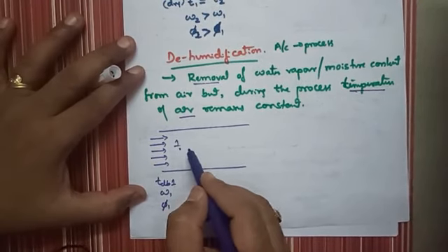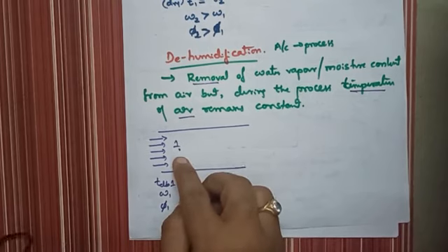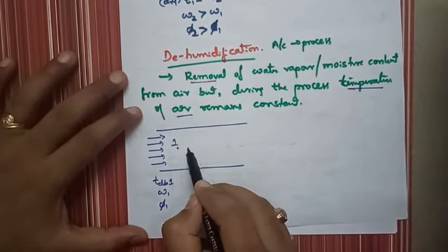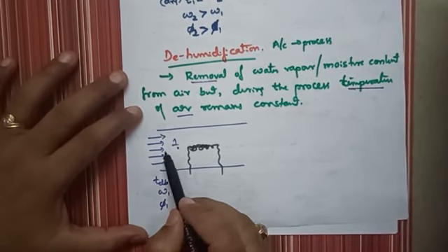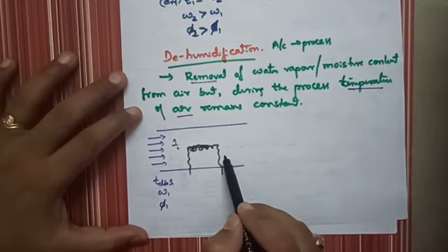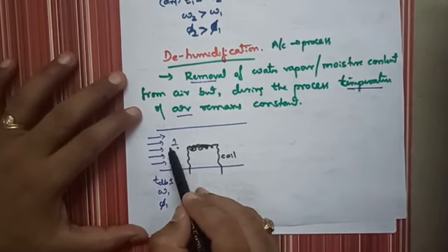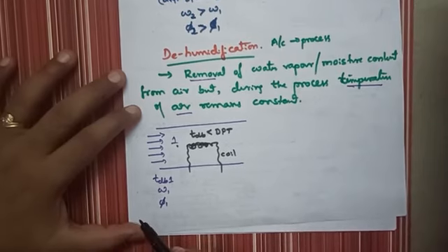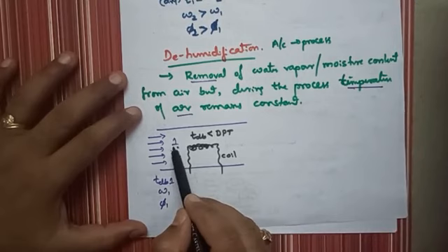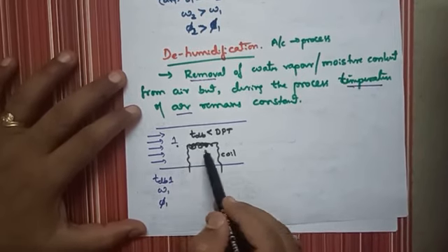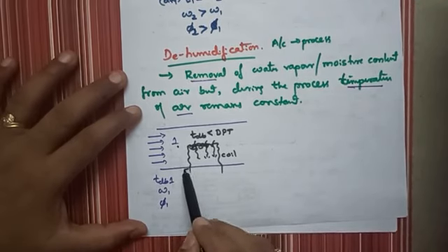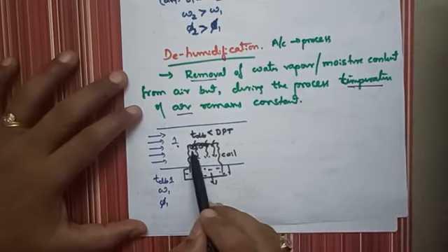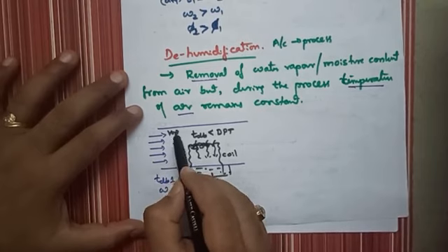To remove the water vapor, an evaporating coil is used. When air touches the surface of this coil and the dry bulb temperature of the air becomes less than the dew point temperature, the water vapor or moisture content in the air starts to condense into liquid. That liquid is collected and removed from the system.